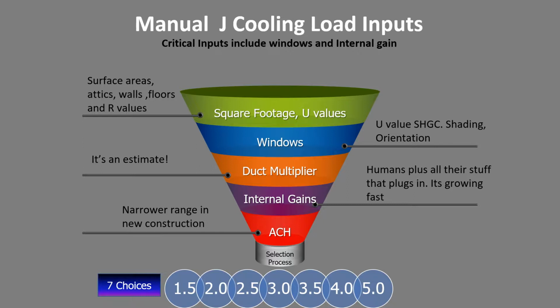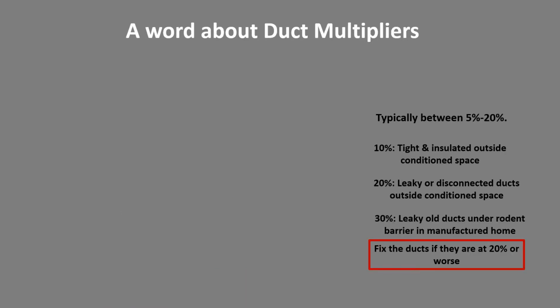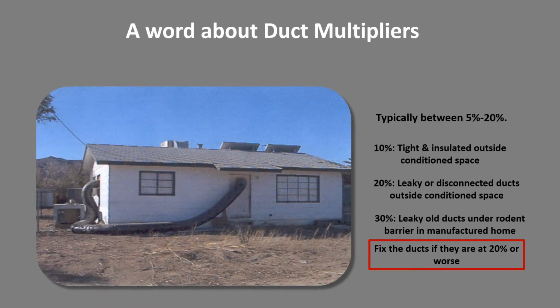And you notice we have a lot more choices when it comes to heat pumps. They come in half-ton increments, which makes the need for precision a little higher. A word about duct multipliers. Yeah, this is kind of a funny picture. It's obviously a test house with a return running outside. But if you think about it, that's probably a more hospitable environment than the attic on this hot day, having it in the front yard.